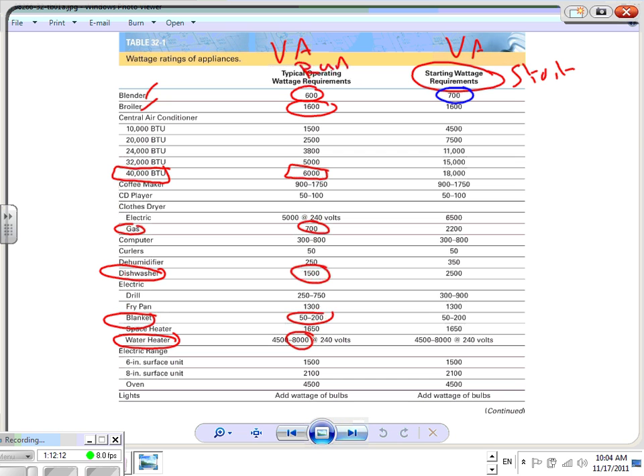Next, look at the blender. It takes 600 watts to run it. But when I start it for 14 seconds, how many watts do I need for just those 14 seconds? 700. The equipment has an inrush, guys. When you have a generator, the generator has to be powerful enough to push things to start. And when things are up and running, it has to be powerful enough to continue running them. The start is just to be able to start the equipment. It takes more power to start the equipment than to run it because of the inrush.